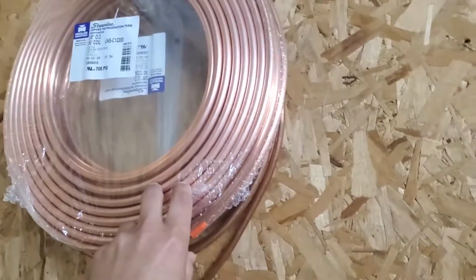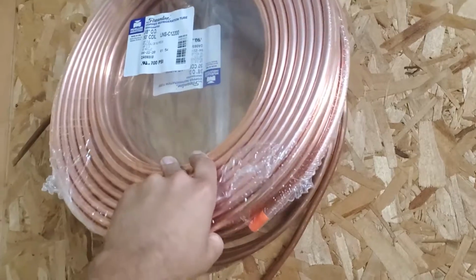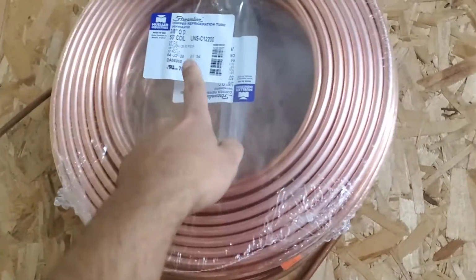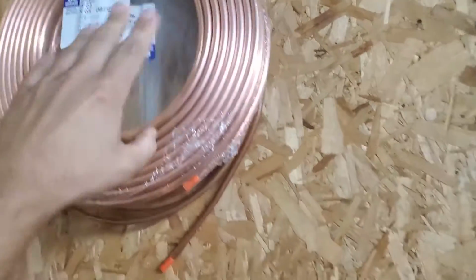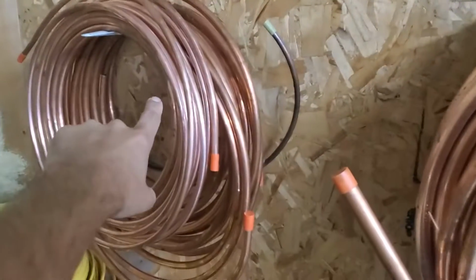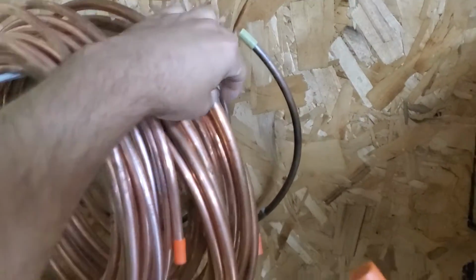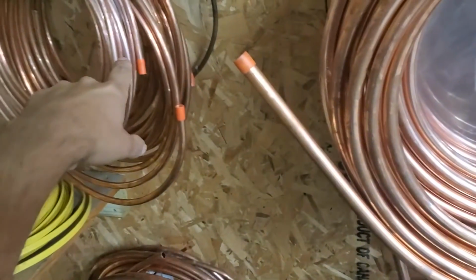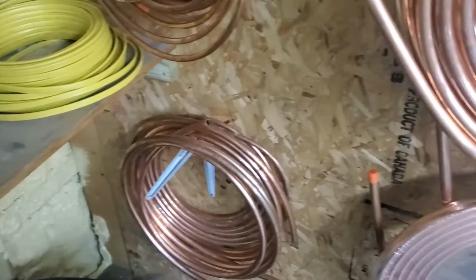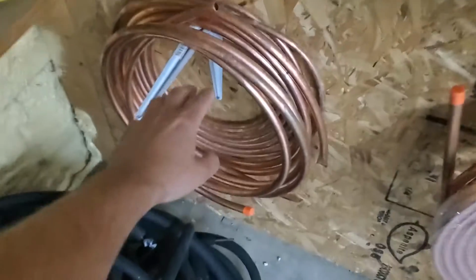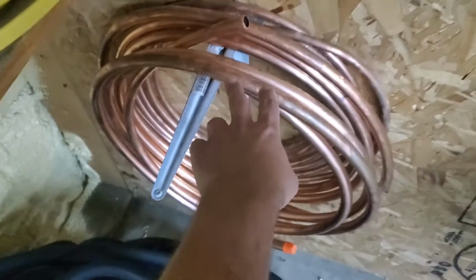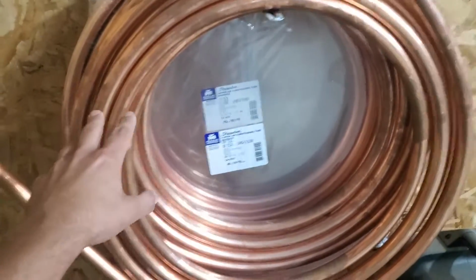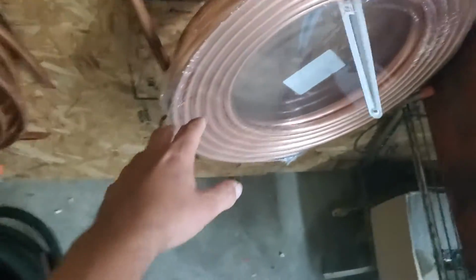So real quick, copper sizes that I'm going to go over that you use most commonly in the field. This is 3/8 copper. This is usually used for the liquid line on residential equipment. You've got 1/2-inch copper. Sometimes that's used in other applications as well. This right here is 3/4 copper. This is usually used for the vapor line. This is 7/8 copper. This is used for the vapor line, but it just depends. It depends on commercial or residential, okay? I'm talking about mostly residential.